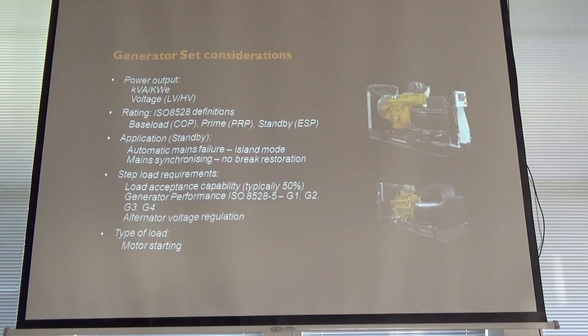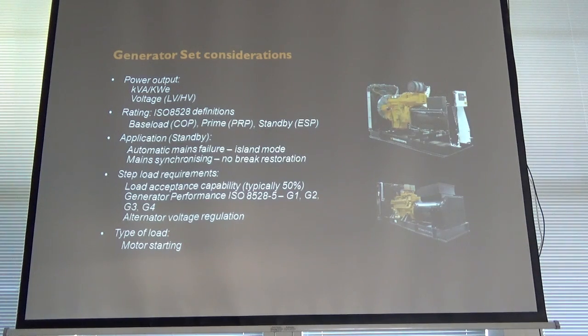The reason why, for a given size of unit, you derate the output, it's literally to do with life of plant. You expect this to last over 15 to 20 years. The key thing with this running period, it affects the engine driver itself. So if you said to me, you could see this KTA 38, 770, if you said to me, I want a generator to run at COP at 1 MVA, that probably means it's a 50 litre engine you'll need, as opposed to a 38. So the key thing is the effect on the engine driver itself, and it's to do with stress of the components, the running and the life of plant.